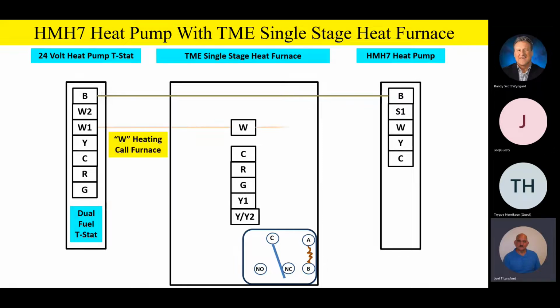And because this is a single stage furnace, we're only going to utilize the W1 on the heat pump thermostat, and that'll go to W on the single stage furnace, and then that'll carry straight outside to W outside. Because remember, team, whenever we go into defrost, we're going to have to bring the heating system on as well during defrost, because when we switch that heat pump into defrost, it's actually going into the cooling mode to defrost it outside, and we don't want to freeze the homeowner out. So we always need to bring on auxiliary heat or supplementary heat during defrost.